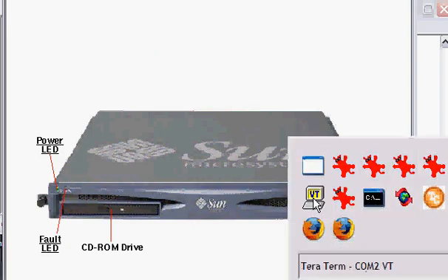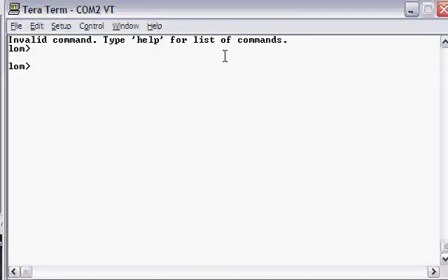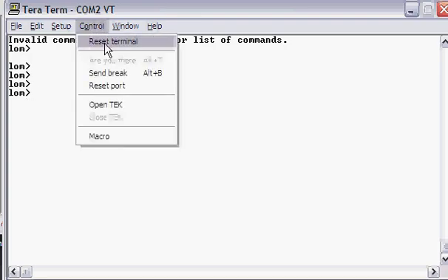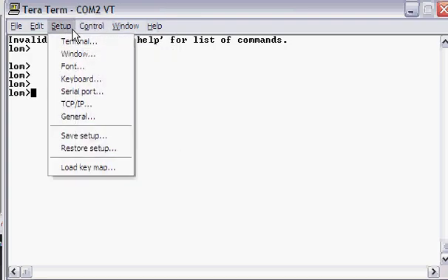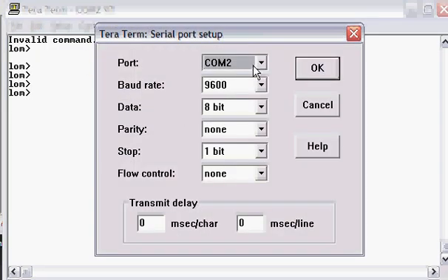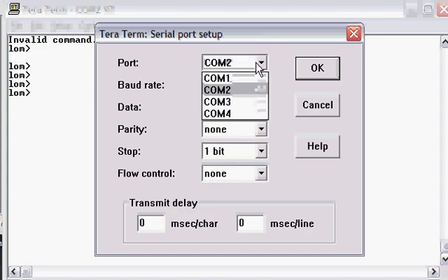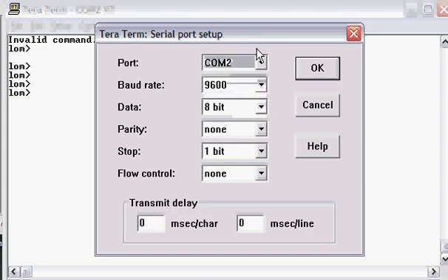Now we can go to the actual, I'm using Tera Term as my terminal emulation program. Currently, I'm attached to the system. My settings were pretty straightforward. Let's go to the serial port. And so I'm on COM2. And if you're using a USB to serial connection, you need to be aware that in the device manager of Windows, you can change the COM port because the COM ports only go up to four on Tera Term. So I had to set my COM port from five to two, and then it's a pretty standard baud rate data parity stop and flow control.